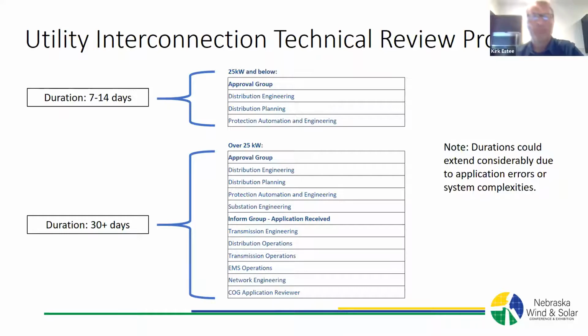For 25 kilowatts and below, there are about three groups that need to look at it. Distribution engineering checks that the transformers and equipment in the area can handle it. Distribution people check that the metering systems are sufficient. And protection and automation engineering makes sure the inverters and automatic devices that shut down during an outage are safe for the frontline crew who have to be out there during storms and similar events.